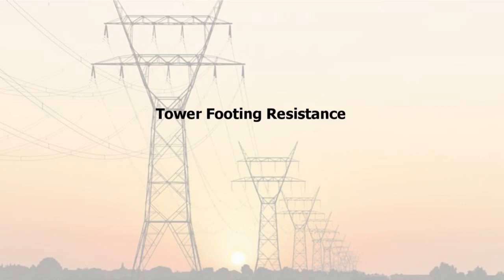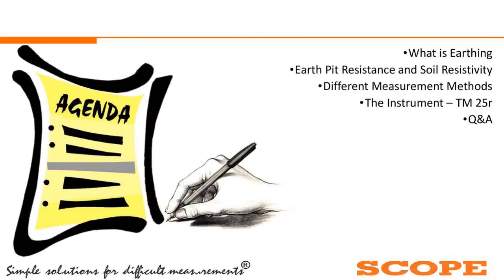So, let us start today's session where we are going to talk about the tower footing resistance measurement. Directly before going to the tower footing resistance measurement, we will be starting with what is earthing, what are the different types of earthing, what is earth pit, what is earth pit resistance, soil resistivity, what are the different types of rods or earthing methods used, then what are the different ways we can measure the earth resistance and resistivity, and finally we will be going into the actual tower footing resistance measurement, their principle, and lastly we'll be completing with a small introduction to our instrument TM25R, the tower footing resistance meter.